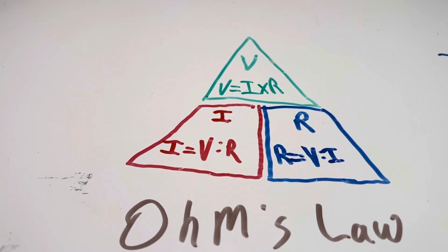You're also going to be experiencing high amp draw. So whatever your rated amp draw is on your compressor and fan motor, add those together, and if your total amp draw is higher than what the rating is, then obviously you've got a problem. You've got high amperage and low voltage. That means that there is something inhibiting the current flow.